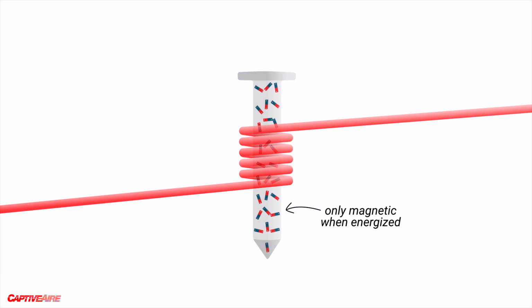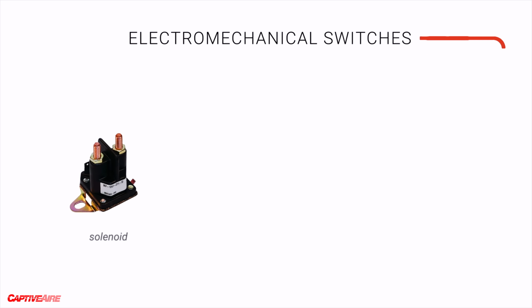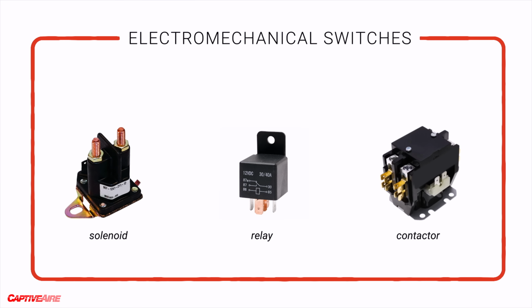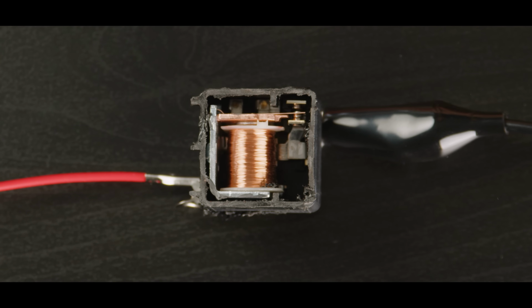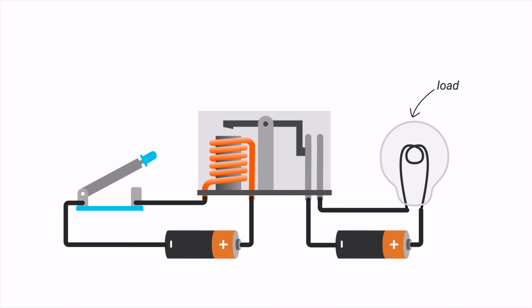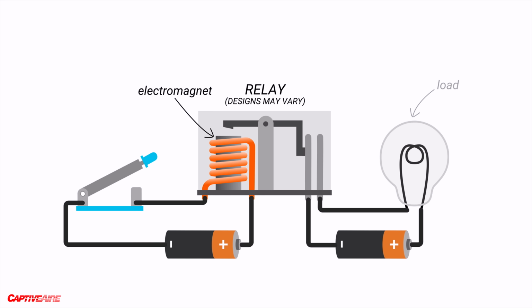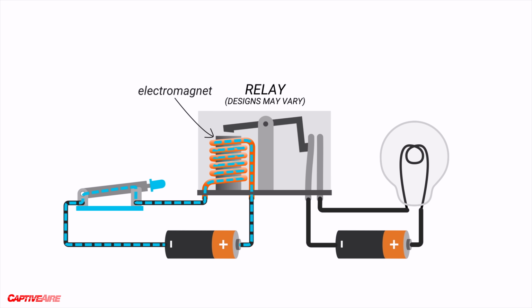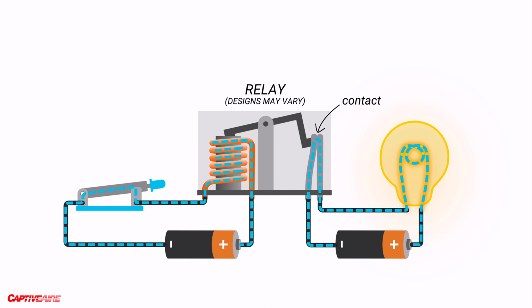This takes us back to our original question of electromechanical switches. Solenoids, relays, and contactors are all kinds of electromechanical switches, and they work on the same basic principle as the wire wrapped around the nail. Imagine we have a load we want to control. In the case of the relay, we have an electromagnet with a static ferrous core, like the nail. When we energize the coil, the resulting magnetic field moves a mechanism that opens or closes a contact. So it's basically a switch, just controlled a different way.